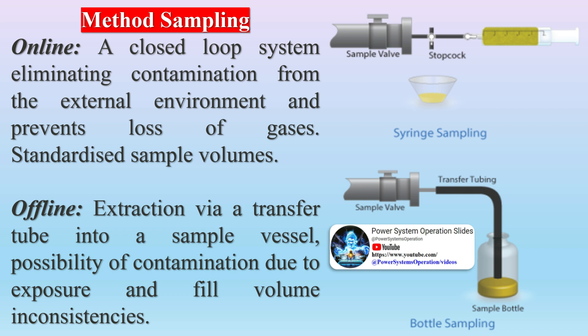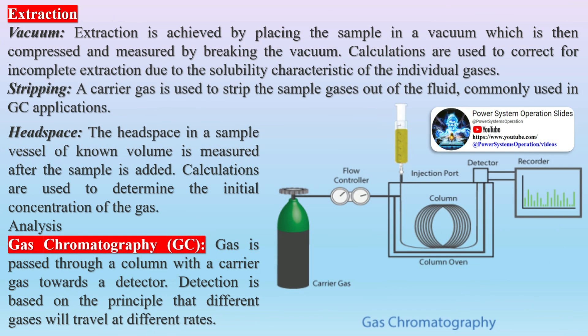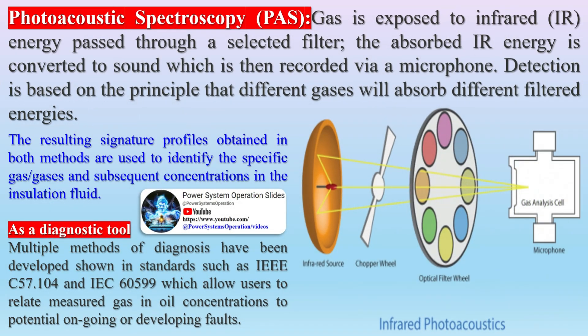Extraction methods include vacuum extraction, achieved by placing the sample in a vacuum which is then compressed and measured by breaking the vacuum; calculations are used to correct for incomplete extraction due to the solubility characteristics of the individual gases. Stripping: a carrier gas is used to strip the sample gases out of the fluid, commonly used in GC applications. Headspace: the headspace in a sample vessel of known volume is measured after the sample is added, and calculations are used to determine the initial concentration of the gas.